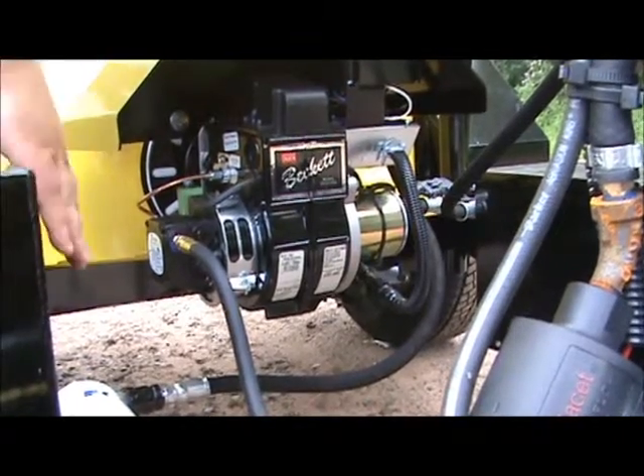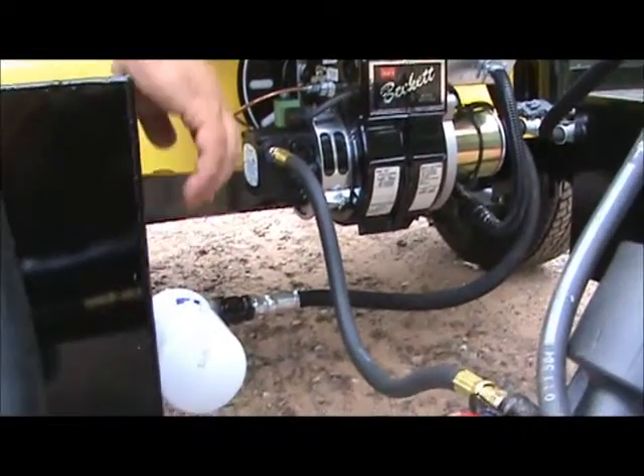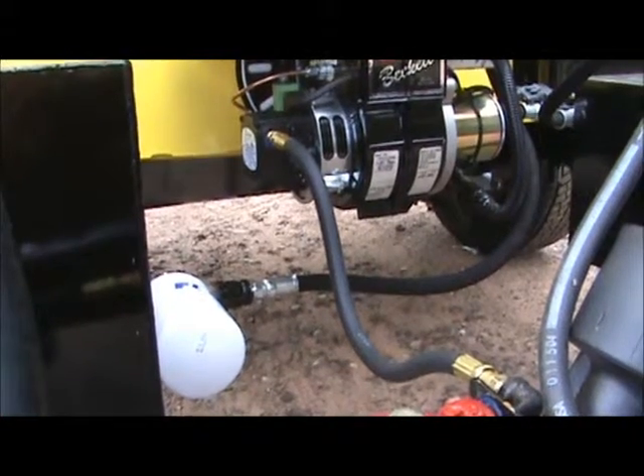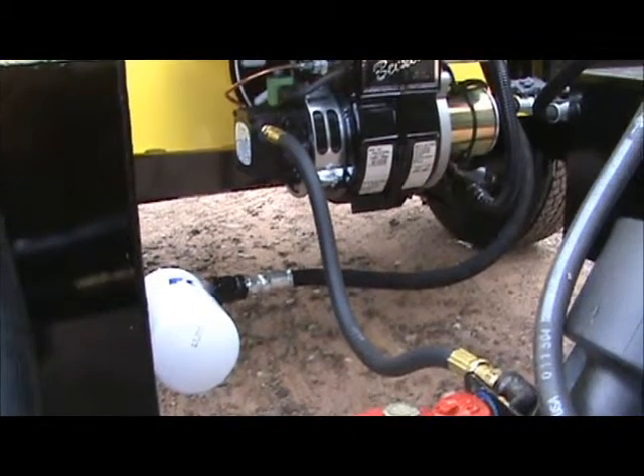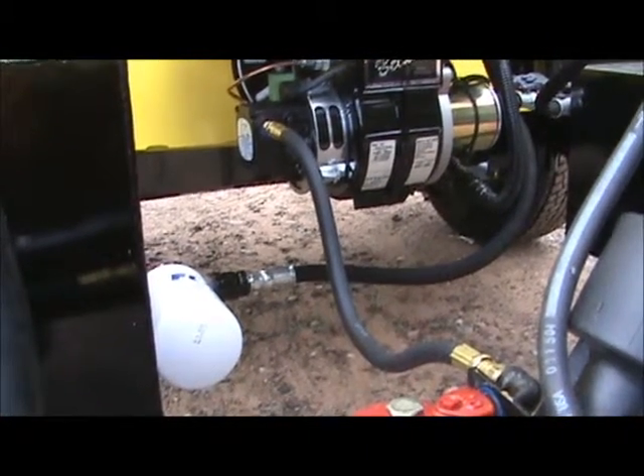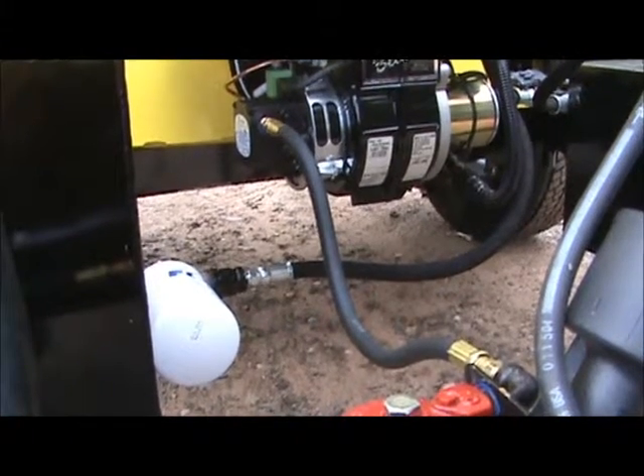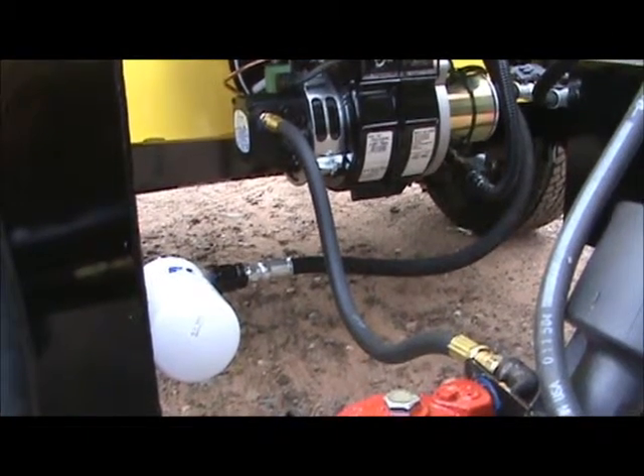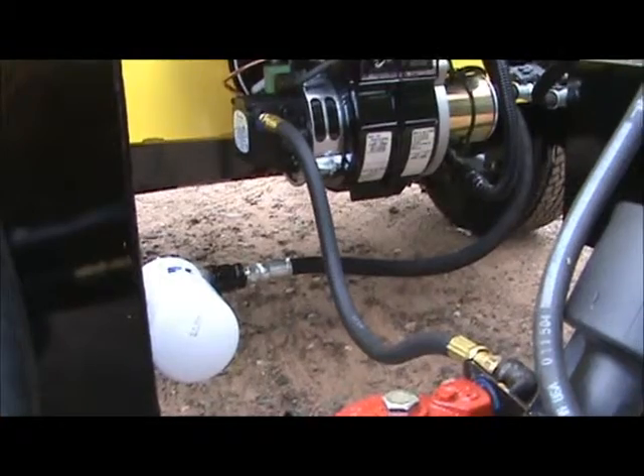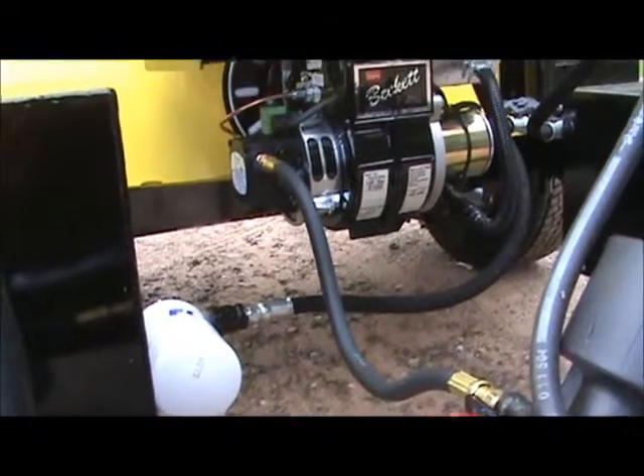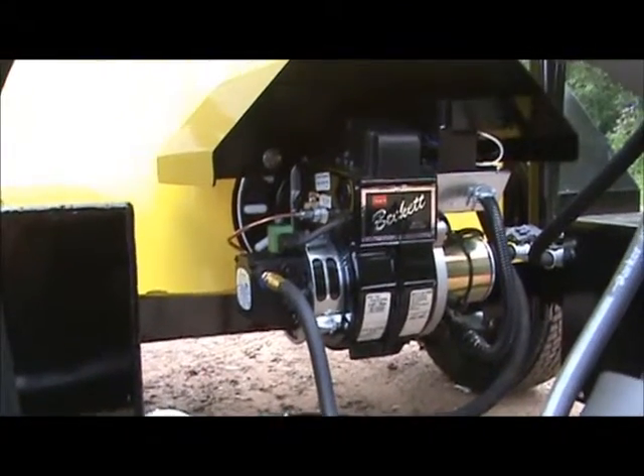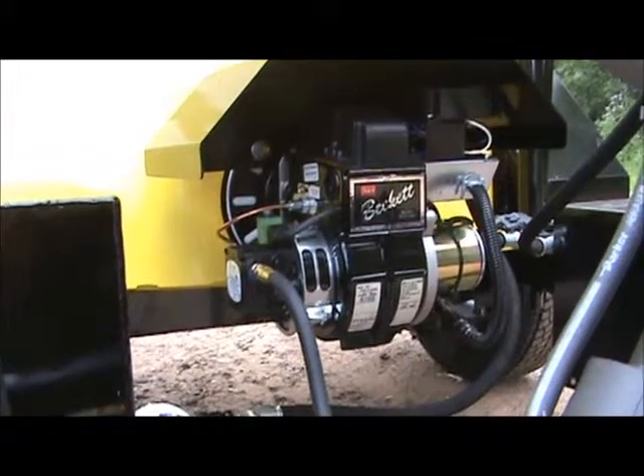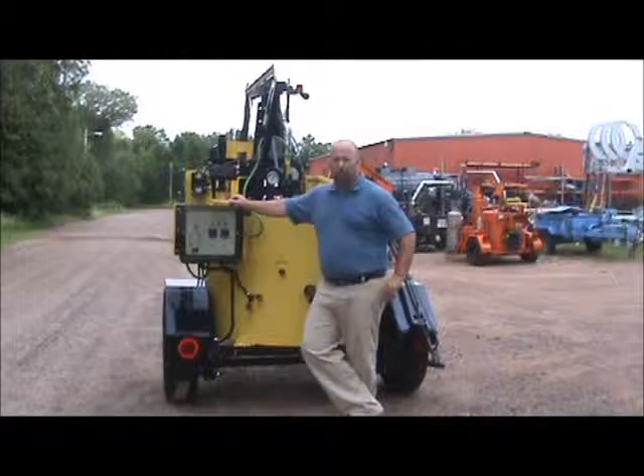Right alongside the burner, you'll see we've got our hydraulic filter. It's just a spin-on type filter. The hydraulic oil is just an all-weather hydraulic oil. There's nothing special about it. You can get it at any local parts store or any oil supplier will have that. We're going to go around to the back of the unit, start going over the controls, and then we'll fire the unit up and show you how everything operates.